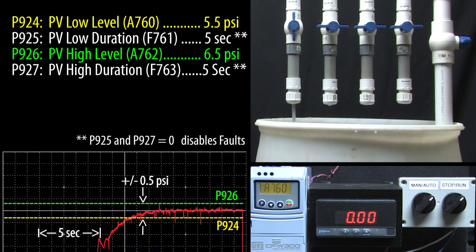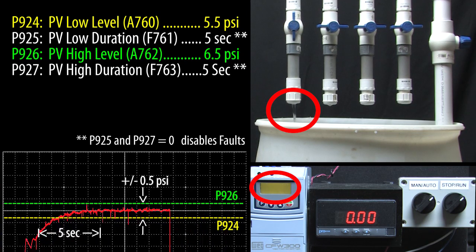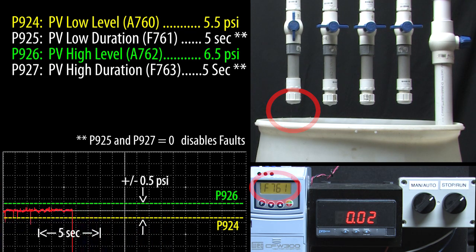I'll short the sensor to ground to simulate a sudden drop in pressure and we get the low pressure alarm. That occurs 150 milliseconds after the condition starts. And then after 5 seconds we get a fault, the drive shuts down its output and the motor goes to a stop. Exactly what we expect.